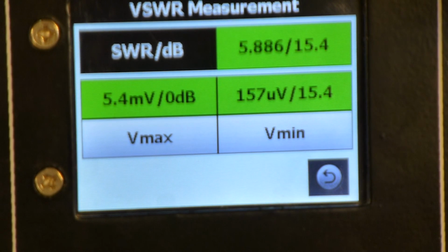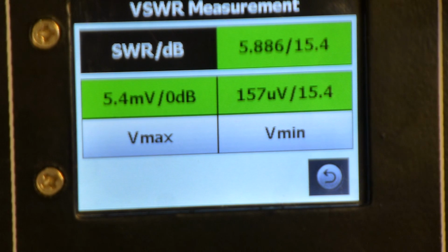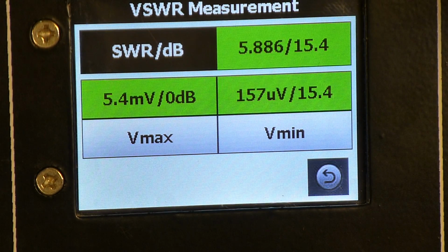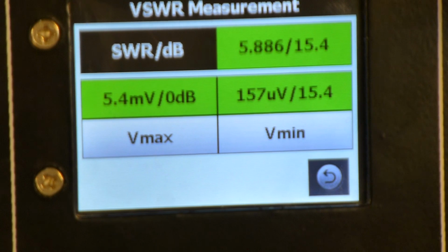The reason being, the measurement of power is done with the help of a detector, which has to work in the square law region, because the Gunn VSWR meter again is a square law device. So this reading will change when we operate the power of the Gunn oscillator in such a way that it comes in the square law region of the detector diode.